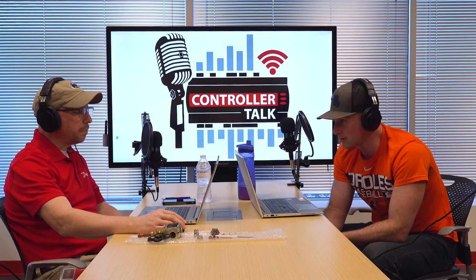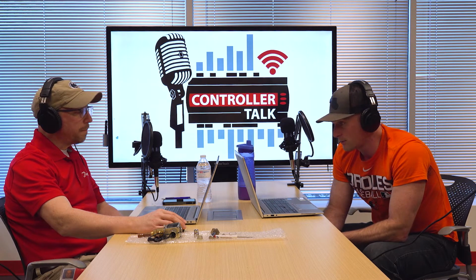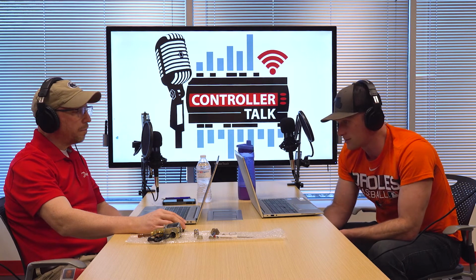Those are some of the things that you're looking at. If you're on the startup and you suspect one of these problems, you can always turn off some other cases that are nearby just to see if that all of a sudden gives you the liquid you need to feed the case that you're troubleshooting. Yep, you can turn off the hand valve if it's got one, or you can just make sure that case isn't feeding nearby. That's right.